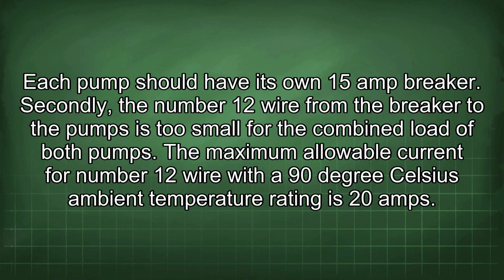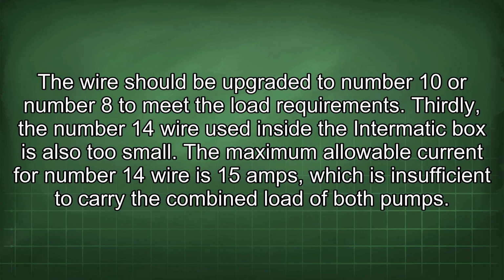Secondly, the number 12 wire from the breaker to the pumps is too small for the combined load of both pumps. The maximum allowable current for number 12 wire with a 90°C ambient temperature rating is 20 amps. The wire should be upgraded to number 10 or number 8 to meet the load requirements.